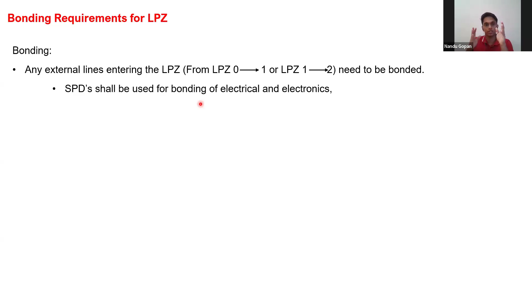So no potential difference - that is why bonding is required first. You are supposed to use SPDs for bonding of electrical and electronic systems. If there are shielded cables or metal ducts coming in, you are supposed to bond those too. If there is any armoring, you are supposed to armor the cable in that zone and bring it out, or if it goes inside an enclosure within LPZ zone 1, for example, you are supposed to bond it in that enclosure and bring it out.